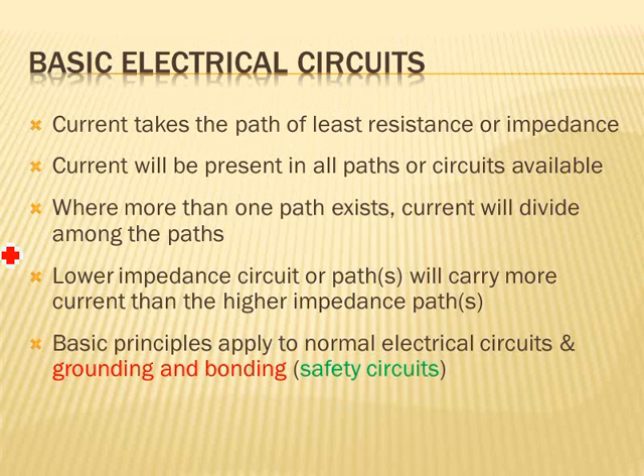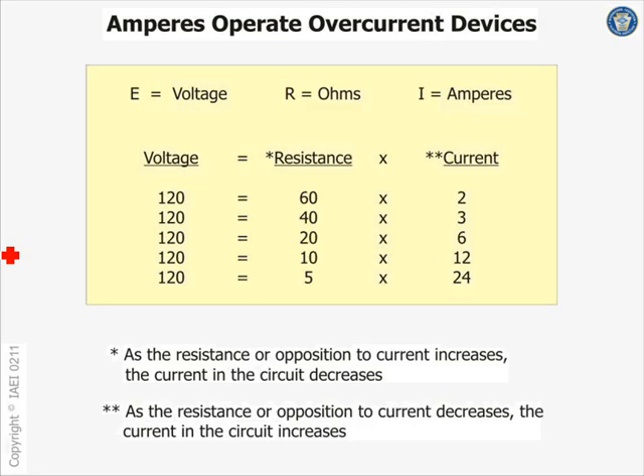Normal operation, parallel series circuit, right? Remember the parallel series circuit? That applies to the normal operation as well as the safety circuit. This is a good example. The higher the impedance, the lower the current. Higher impedance, can you see? Lower current. If the impedance starts going down, the current goes up. That's why they don't allow us to depend on Mother Earth as a return for our ground fault, right? Why? Because Mother Earth could be high impedance. What happens with high impedance? Lower current. What happens with lower current? The circuit breaker wouldn't wake up. It wouldn't see it before it starts arcing and sparking and burns the building. So that concept of the higher the impedance, the lower the current is very powerful for many reasons. For the safety guys, we need our path to be low so our current can be high, so the circuit breaker wakes up and trips and saves my building from being burned.